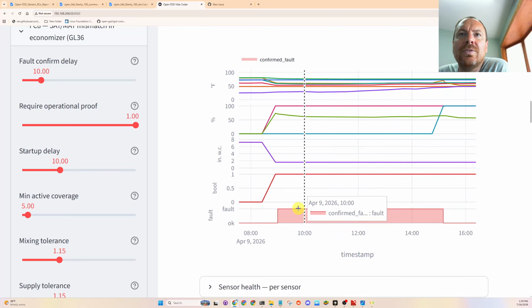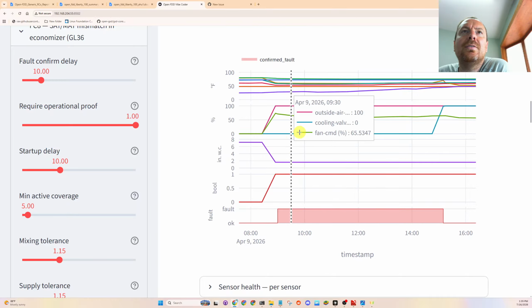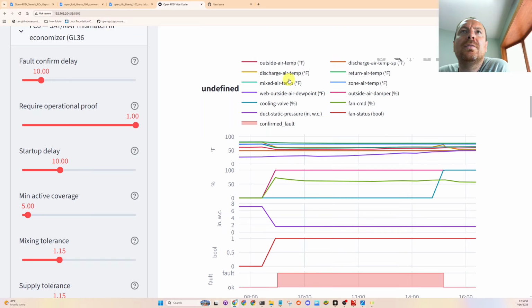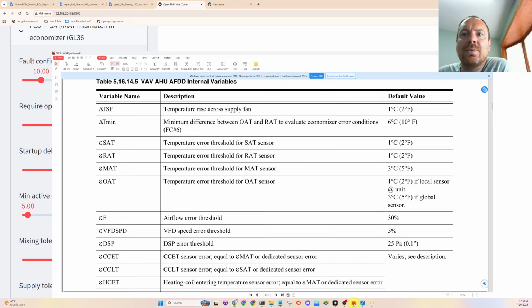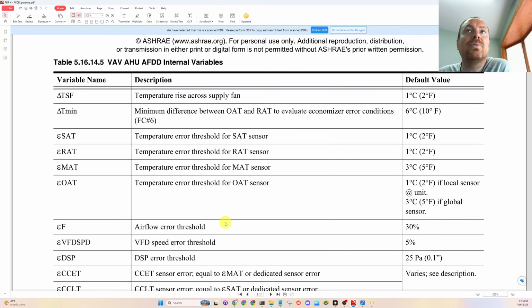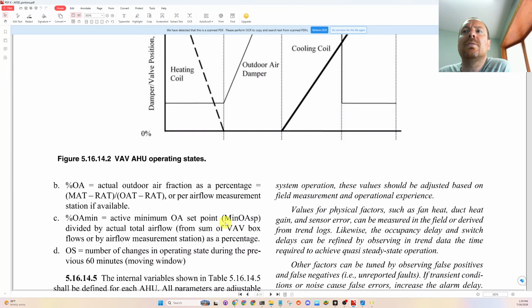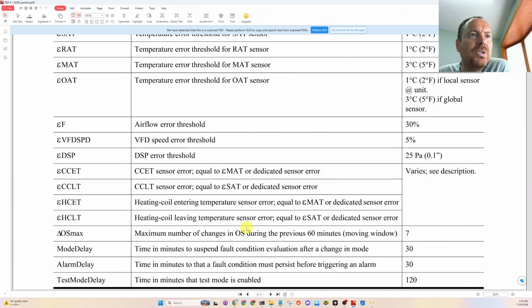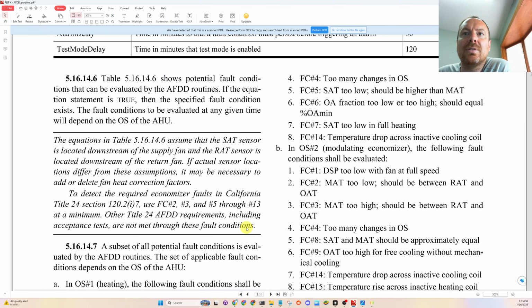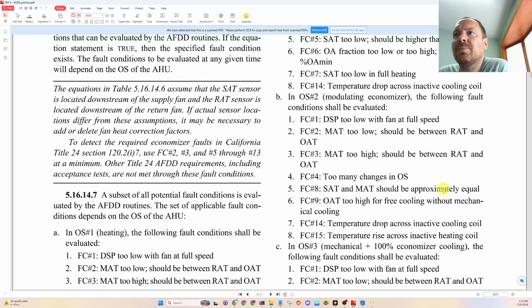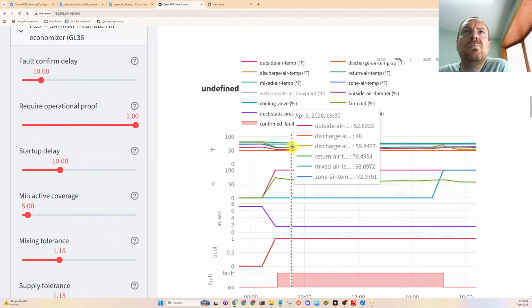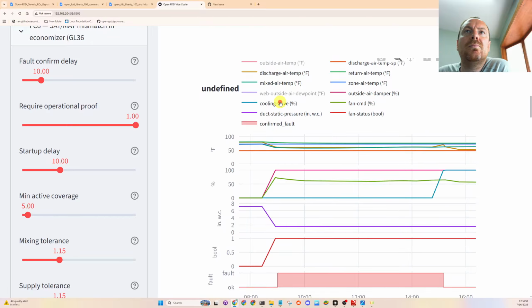Okay, so if we have a confirmed fault, basically we want to see that the mixed air temperature should be approximately equal to supplier temp. Jumping around here a bit. Fault condition 8: supplier temp and mixed air temp should be approximately equal. We have outside air damper.